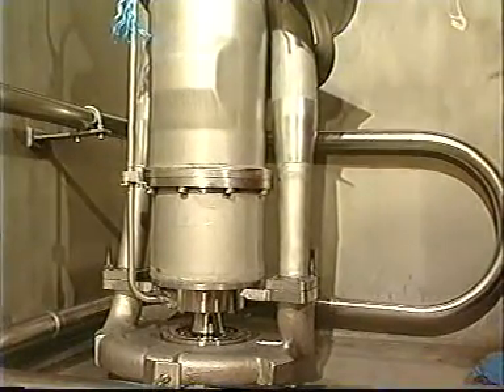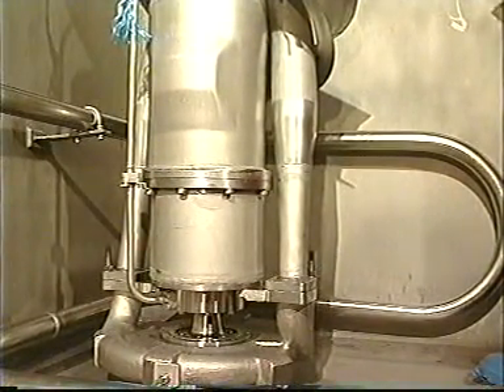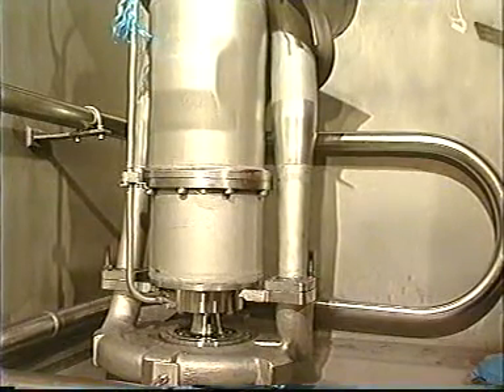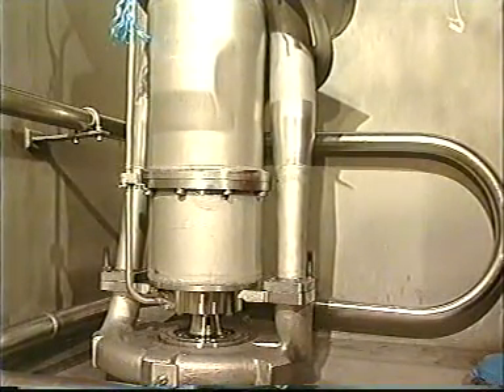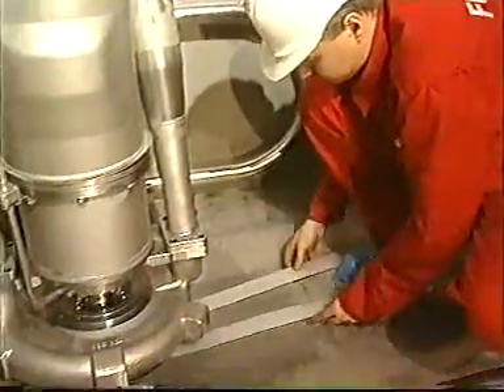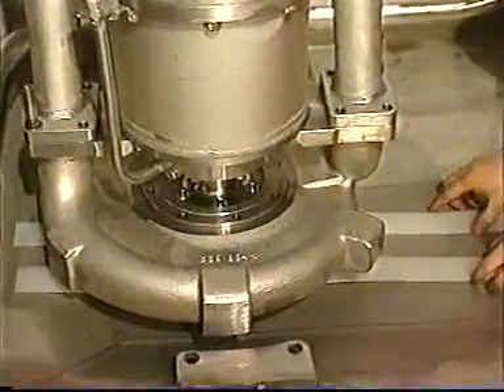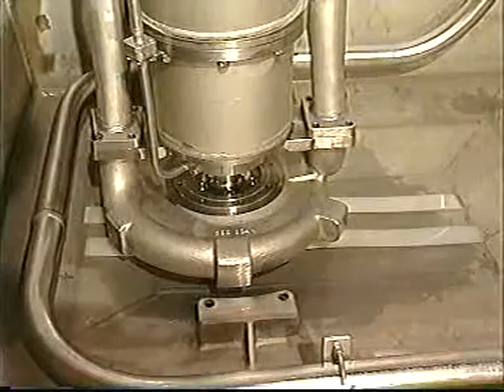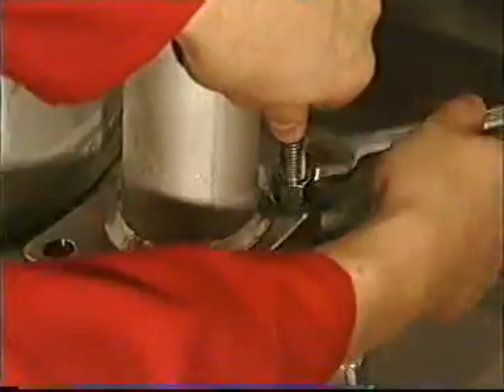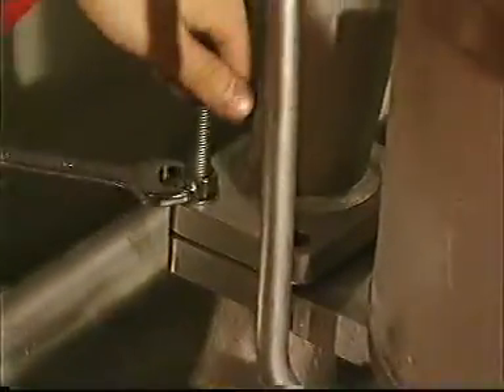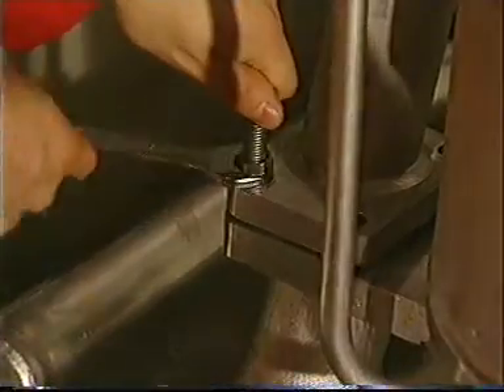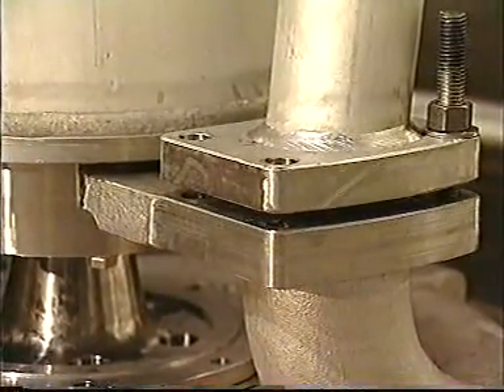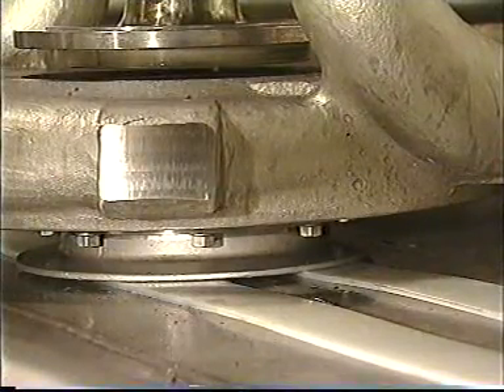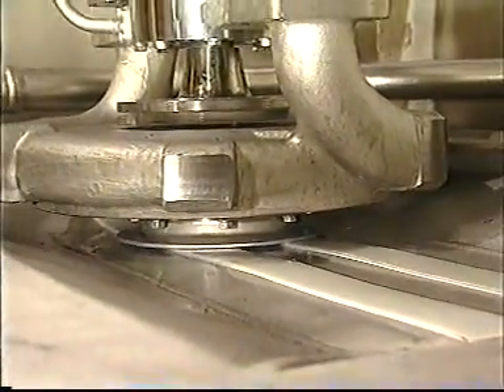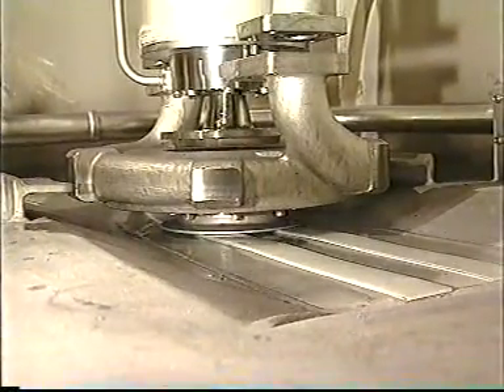Finally, the volute casing, suction cover and pump impeller is now hanging in the lowering, lifting bolts, diagonally positioned on each cargo leg. To avoid damage on the tank top, use plastic strips when sliding out the unit. Lower the whole unit down carefully, turn the lowering, lifting bolts in parallel. Slide the unit out of the well.